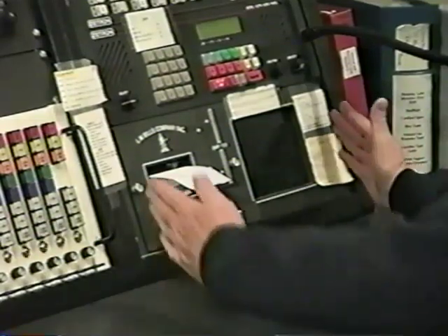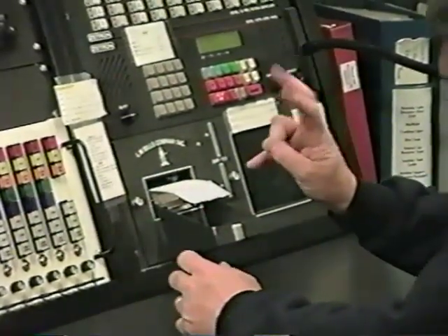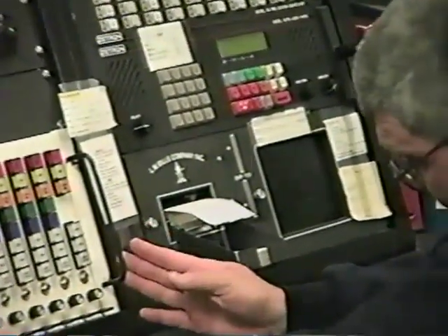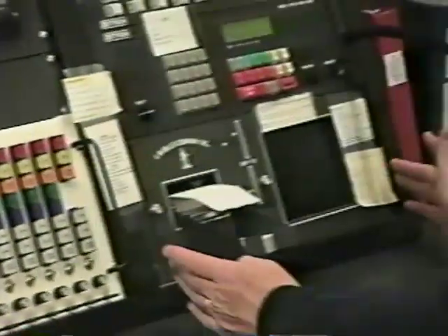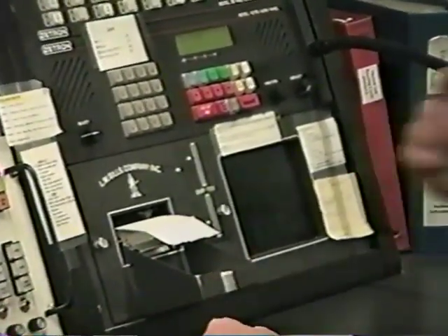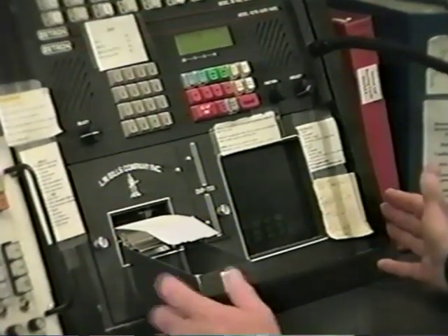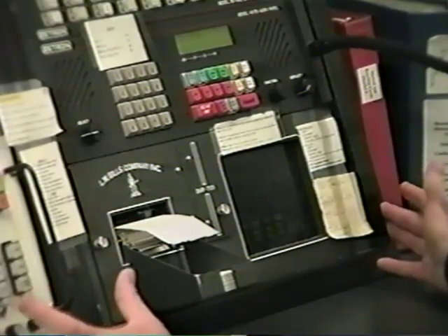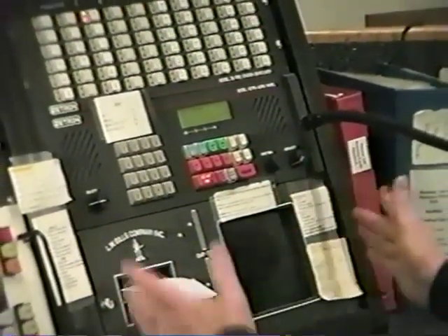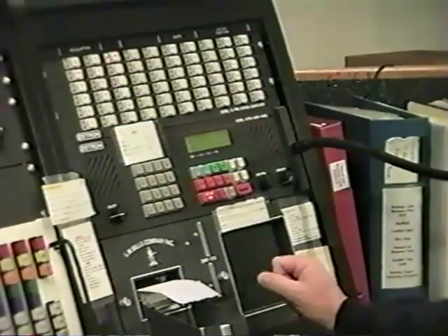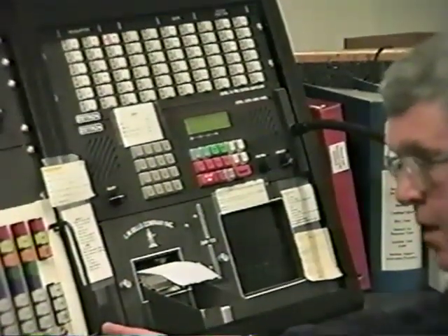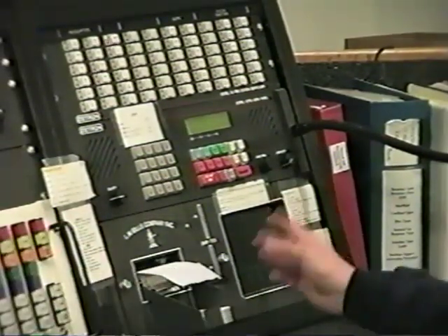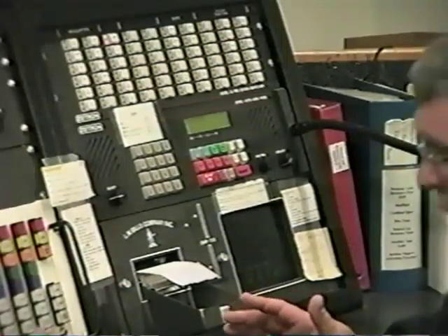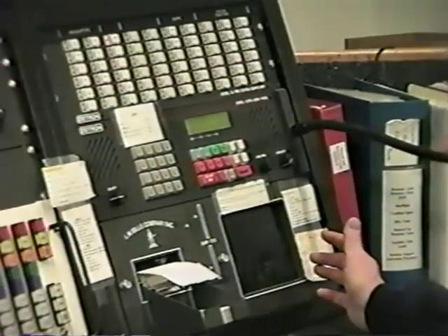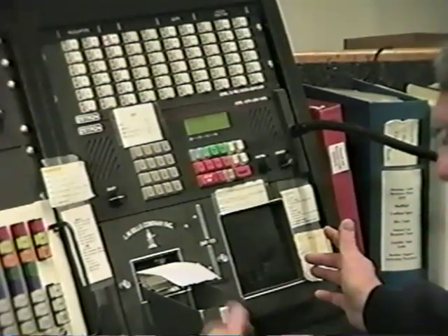The Keltron, which is this piece of equipment right here, is capable of two functions. It'll receive the box alarms from the municipal fire alarm system, and it'll receive central station alarms. The Wilmington Fire Department runs their own central station. And this is a phone dialer that people mount in a fire alarm panel at the company. And when the fire alarm trips, it dials up a number that comes into here, and the information will print on the screen. It can be backed up by a master box, and that would come in at the same time. These would blink, this thing would print, and we would get the alarm from both. They're redundant, but one backs up the other. If the telephone lines are down, the fire alarm lines are going to probably be still working, or vice versa.